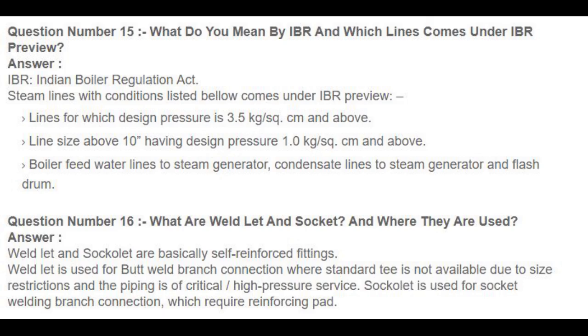Question number 15: What do you mean by IBR and which lines come under IBR preview? Answer: IBR — Indian Boiler Regulation Act. Steam lines with the following conditions come under IBR: lines for which design pressure is 3.5 kg/cm² and above; line size above 10 inches having design pressure 1.0 kg/cm² and above; boiler feed water lines to steam generator; condensate lines to steam generator and flash drum.